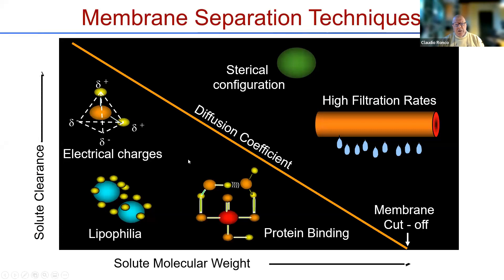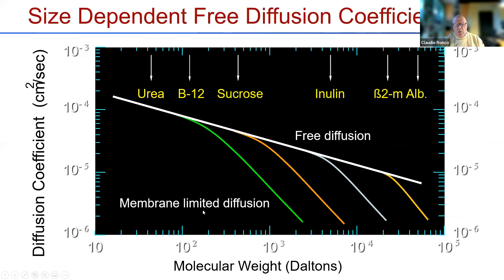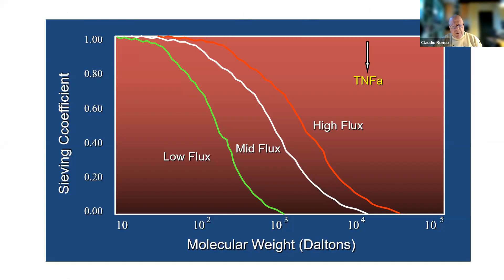In mass separation techniques by barrier, we mostly use diffusion. But the free diffusion coefficient decreases progressively as solute molecular weight increases. You may have a different impact depending on protein binding, high filtration rates, or electrical charges. But basically, for larger solutes, diffusion is not efficient. And if you impose a membrane to the free diffusion in water, you further reduce the free diffusion coefficient through the membrane. So another method is required, and it is convection.